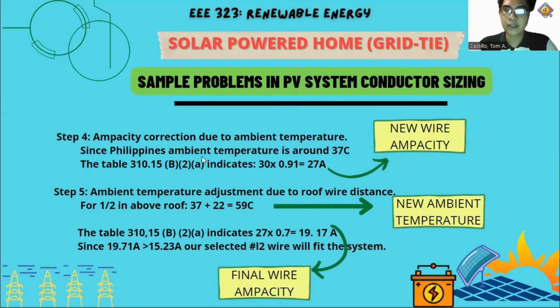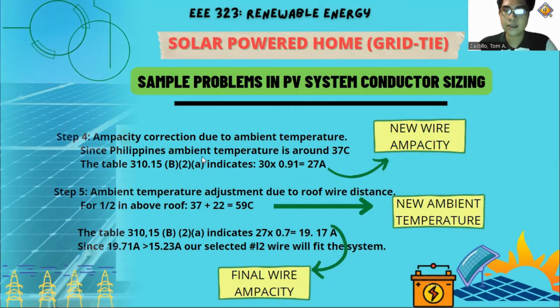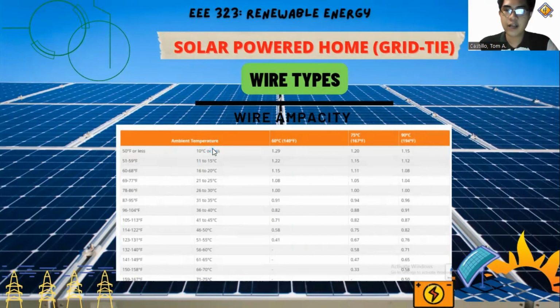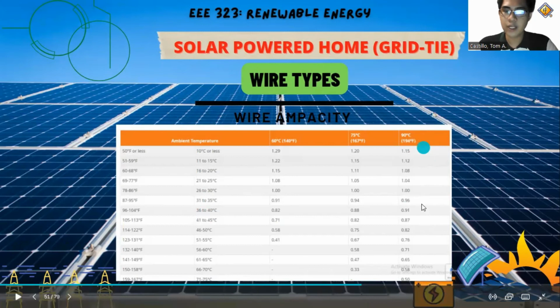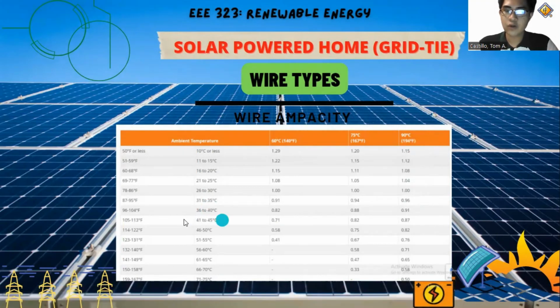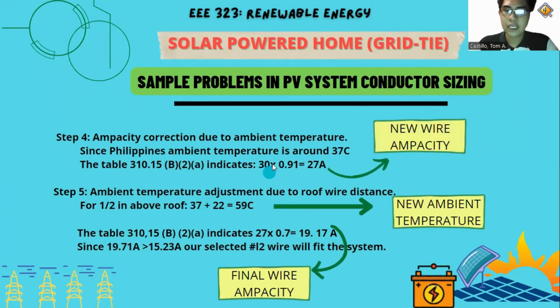So, ano ba yung multiplier natin para malaman natin yung new wire ampacity? So, since Philippine ambient temperature is around 37 degrees Celsius, saan ba siya pasok? So, dito siya sa 36 to 40 degrees Celsius. So, yung wire na pinili natin kanina is 90 degrees Celsius. So, dito tayo pipili. Since pasok yung 37 degrees Celsius dito sa 36 to 40 degrees Celsius, ang magiging multiplier natin is 0.91. So, yung 30 amperes na capacity natin kanina, ito times natin siya sa 0.91. So, bali 27 amperes yung new wire capacity natin.